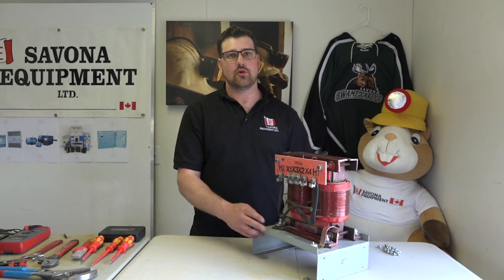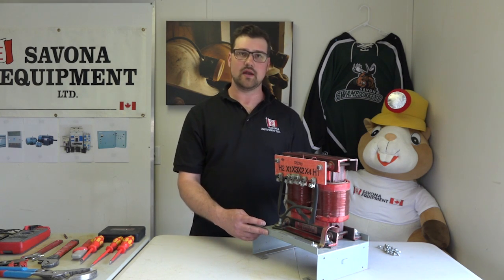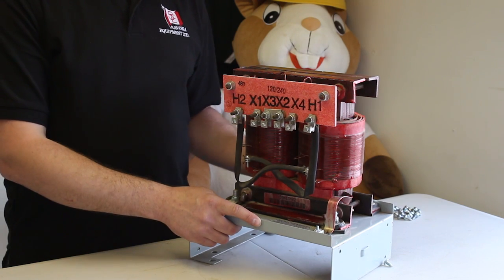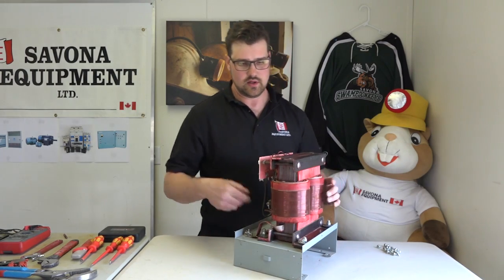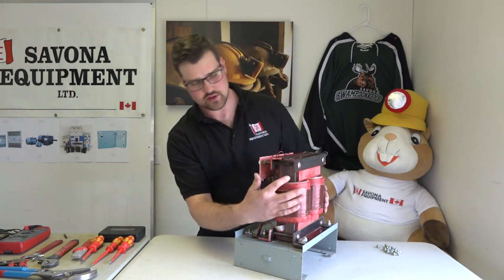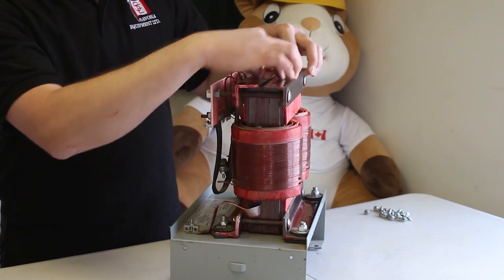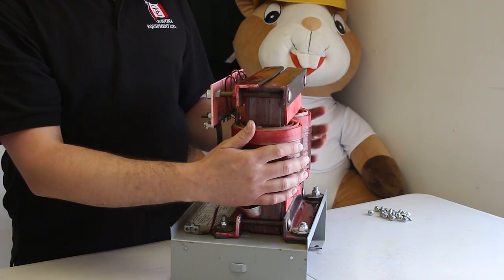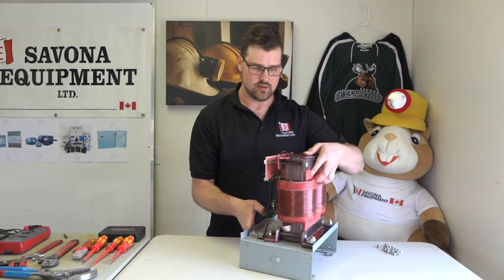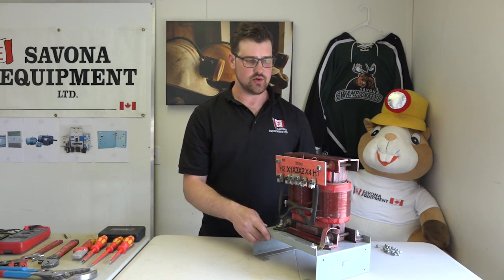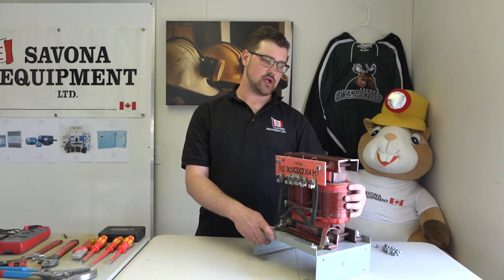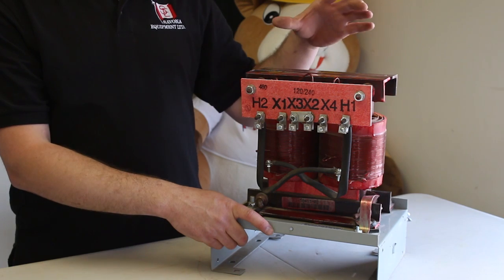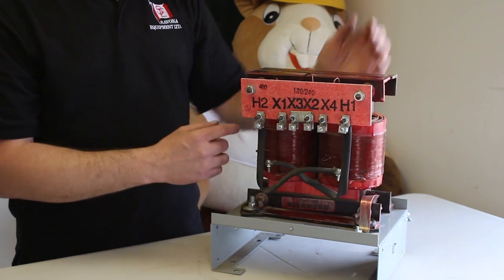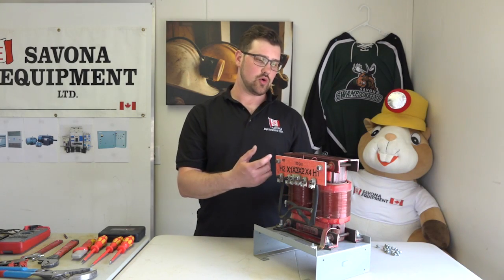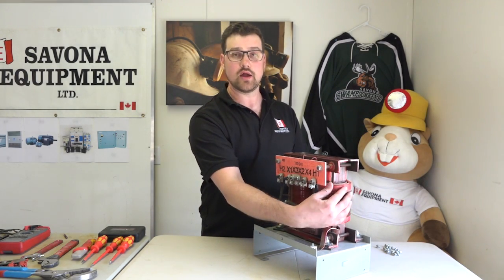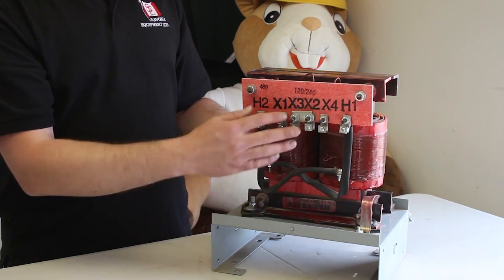So now that we have the transformer opened up, we can have a better look at what a transformer is made of. This one in particular is just the 2 coils. What we have here is an iron core, and you can see it here. This is your iron core. It's connected together, and it goes through both separate windings on this transformer. The way the electricity travels is through electromagnetic induction, and that's how a transformer works. You put the electricity on the high side, 480 volt, and it travels through these coils around the iron core and, the way that these windings are wound, produces the low voltage 120/240.